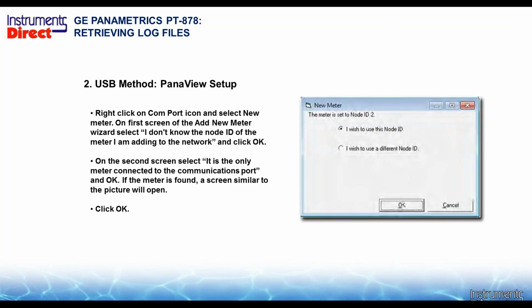So here we need to right-click on the COM port icon and select New Meter. On the first screen of the Add New Meter wizard, you need to select I don't know the node ID of the meter I'm adding to the network, and click OK. On the second screen, select the only meter connected to the COM port, and click OK. If the meter is found, a screen similar to the picture on the right will open. If it doesn't find it, time to go to lunch.